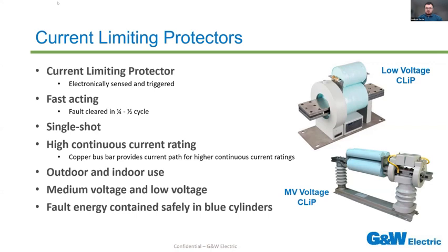When those pyrotechnics blow and those fuses in parallel melt, you do need to go in and replace those blue cylinders that you can see on the images to the right. It's a fairly simple process to do so. There's some bolts on both sides of the interrupter you need to take out, some wires you need to detach. You just go and replace the CLIP, reinstall the wires and hardware, and you go into the control box that's associated with that 3-phase CLIP unit, and then make sure everything's turned on again.